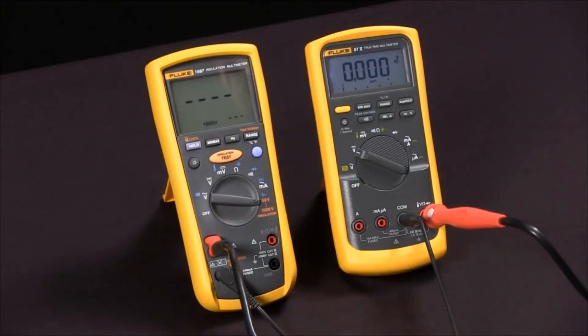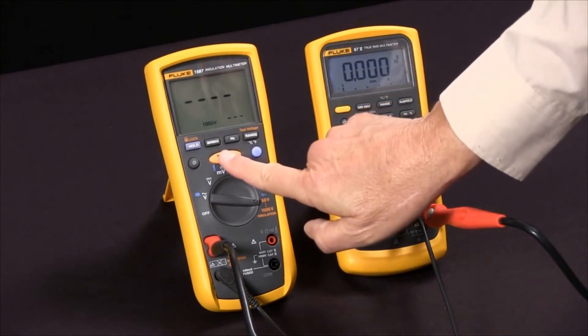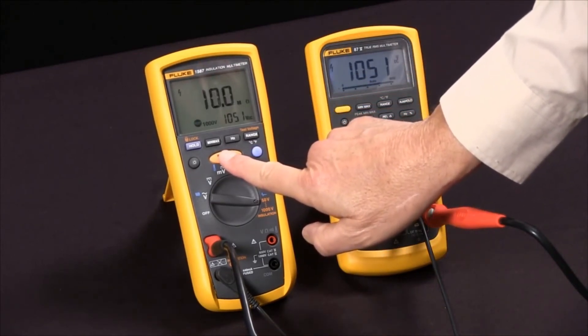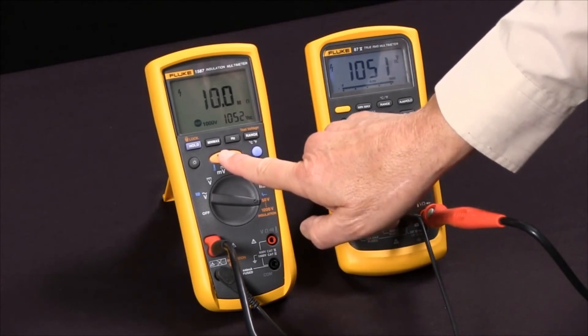And now we're ready to do our test and I'll press the test button and you'll see it apply in this case 1,052 volts and read 10.0 mega ohms.